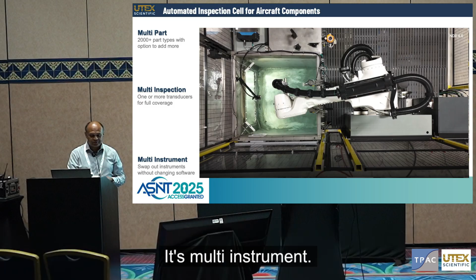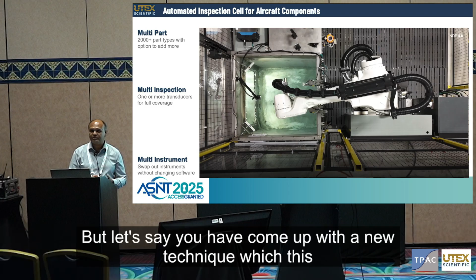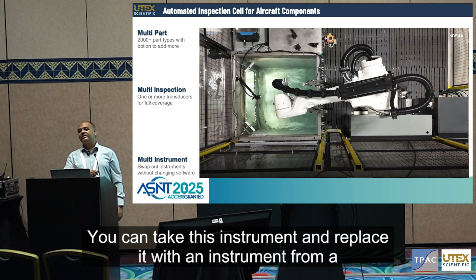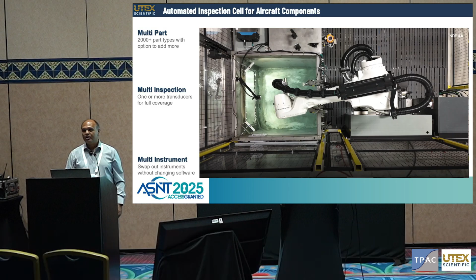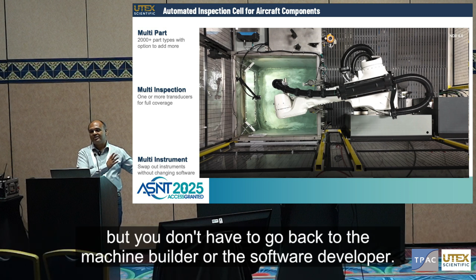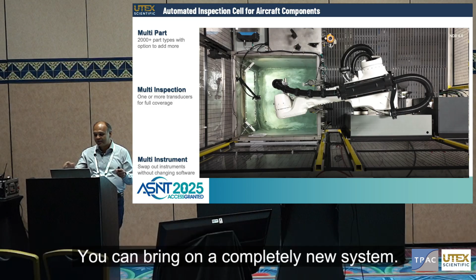And then that's the big one: it's multi-instrument. I really love this instrument, but let's say you've come up with a new technique that this instrument doesn't support. You can take this instrument and replace it with one from a different vendor altogether, and nothing changes on the automation end. You still have to requalify the machine or system, but you don't have to go back to the machine builder or the software developer. Everything is fully under your control, and you can bring on a completely new system.